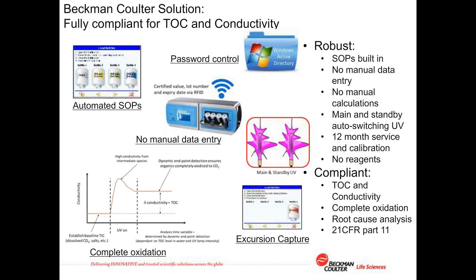So to summarize, the PAT700 TOC and conductivity analyzer from Beckman Coulter is designed to be robust with all necessary SOPs built in and automated. There's no manual data entry or calculations, and uptime is maximized by having auto-switching main and standby UV lamps. There's a 12-month service interval and calibration interval, and it needs no reagents. It is designed to be fully compliant for both TOC and conductivity, as it ensures complete oxidation to get accurate TOC results every time.